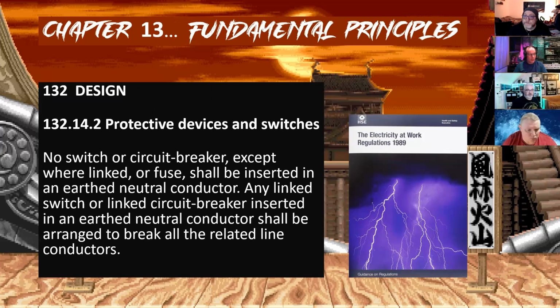Next one, Paul. Okay, so 132.14.2, protective devices and switches. No switch or circuit breaker, except where linked or fused, shall be inserted in an earthed neutral conductor. Any linked switch or linked circuit breaker inserted in an earthed neutral conductor shall be arranged to break all the related line conductors. So we're talking about earth neutral conductors, we're talking about PEN conductors - TNC system, CNE conductors, combined neutral and earth conductor, PEN, protective earth neutral.